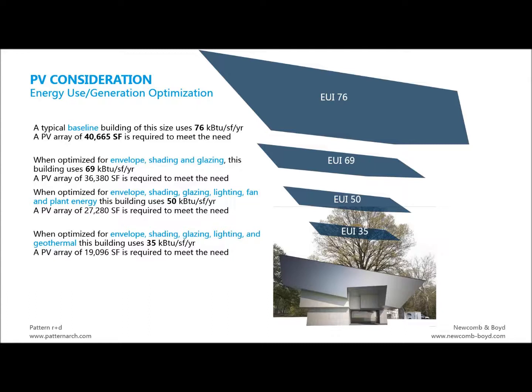And that takes us down to 35 kBtu. Now, that would be for a full geothermal system. In the south that gets tricky because we're cooling dominant, which means you have to size it appropriately so you don't overheat the loop. That takes a lot of land and a lot of cost, and that may actually be more costly than your PV.